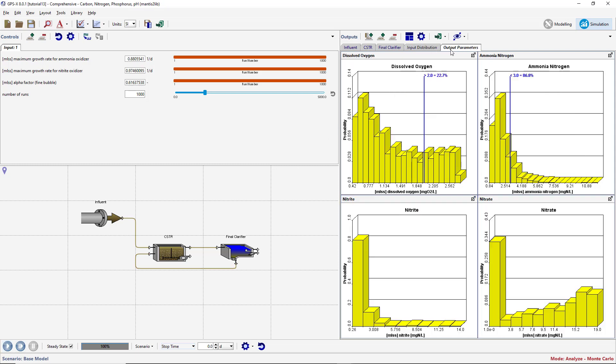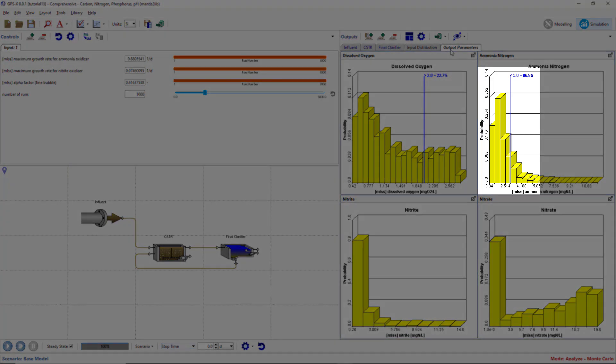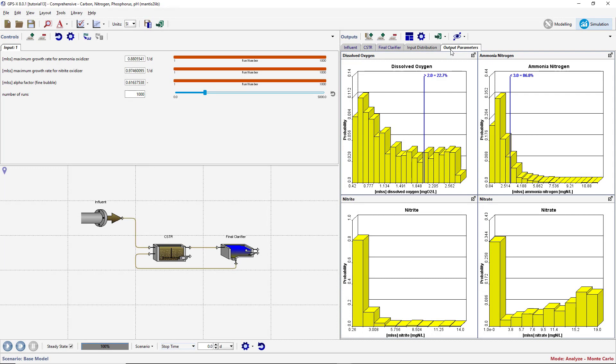Running additional simulations would be more representative of the desired distribution. The graphs on the Output Parameters tab show the performance of the plant under varying inputs. The effluent ammonia graph illustrates that the plant is nitrifying under most conditions. The target line shows the percentage of time that the ammonia is less than 3 mg per liter. Note that you might receive a slightly different Monte Carlo analysis solution, but the percentage of simulations satisfying the ammonia target should be between 85 and 90%. You can create a new scenario to see the effects of increasing the aeration capacity. Try increasing the aeration tank volume and the airflow to the system to see how they affect the distributions. You can also look at the effect that the number of Monte Carlo runs performed has on the distributions.